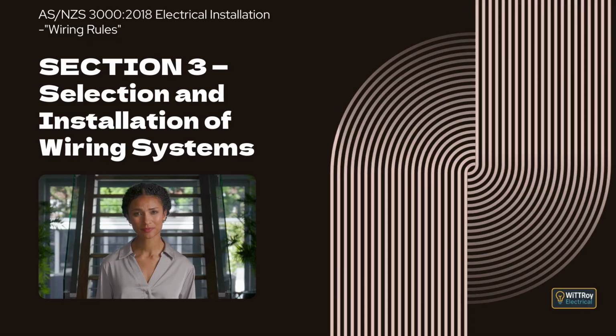Clause 3.8.2.3, Sleeving of existing live conductors. This clause explains that existing live conductors with yellow insulation may remain, but where new terminations or joints are made, white sleeving must be applied at those new points. Clause 3.8.3, Exceptions and special applications. This clause introduces situations where the standard color rules do not apply. Clause 3.8.3.1, General. This clause explains that the standard color identification rules may be relaxed for specific applications covered in the following clauses. Clause 3.8.3.2, Protective earthing and equipotential bonding conductors.